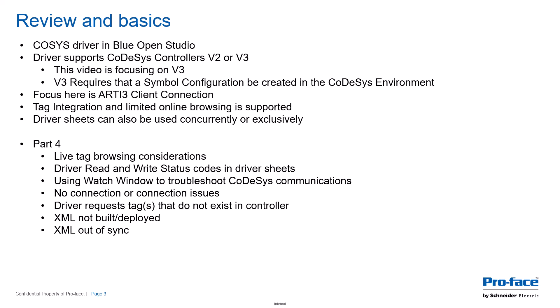We'll also look at some scenarios involving the XML or symbol configuration - specifically when the symbol configuration or XML file has not been configured in the CODESYS controller, or it's the wrong one. So we're out of sync: we've got a specific XML that we're syncing up to create our variables in our Blue Open Studio environment, but that is out of sync with the PLC - and we'll look at what actually happens there.